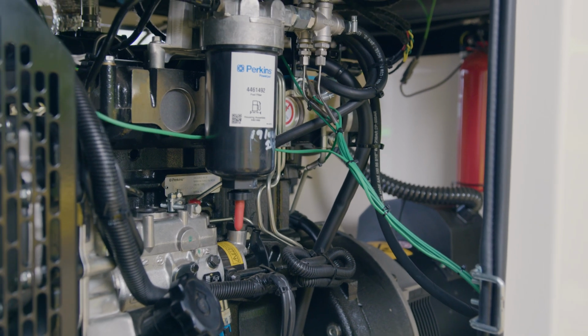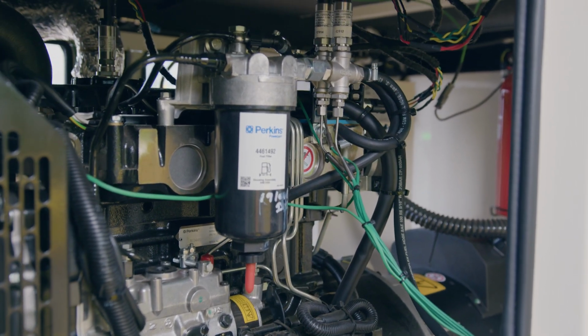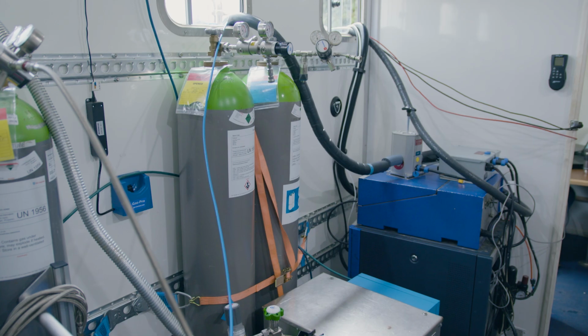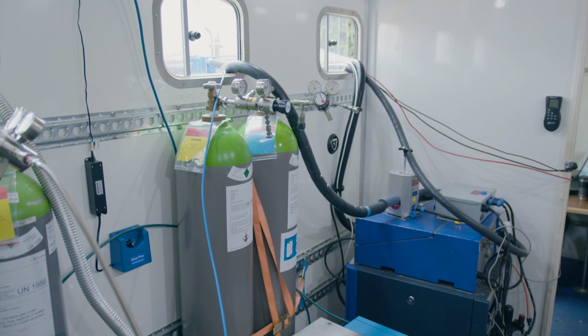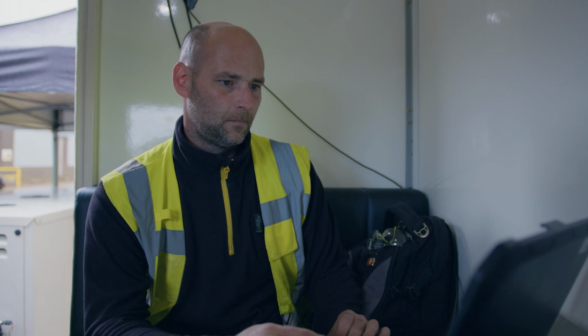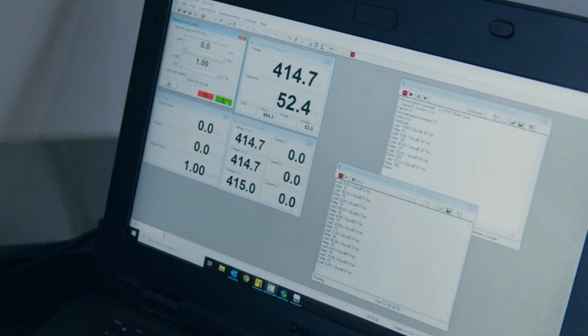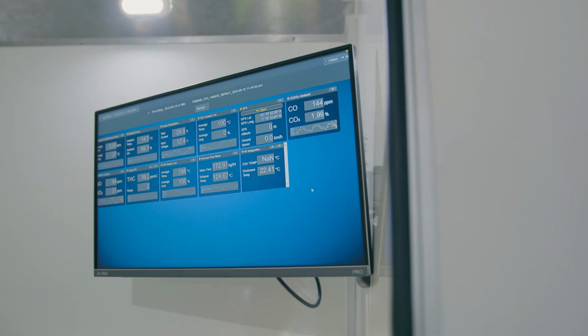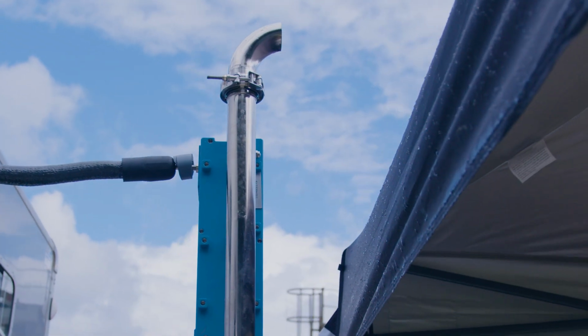It also meant we could repeatably run the test and take those emissions measurements, and by using a load bank, repeatably look at the load acceptance. The set's been running on HVO, the hydrotreated vegetable oil. During that testing, we've taken various measurements during the operation - at 0 hours, 250 hours, 500 hours, and then at 1,000 hours. At each of those points we've measured fuel consumption, load acceptance, and the exhaust emissions that come out of the tailpipe.